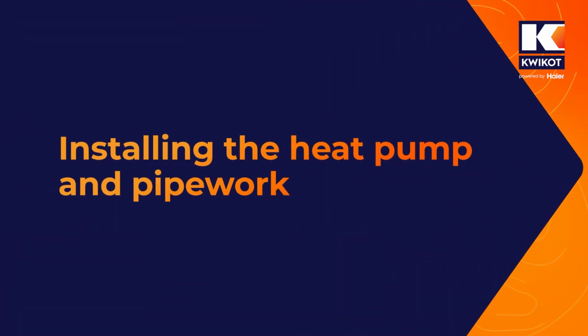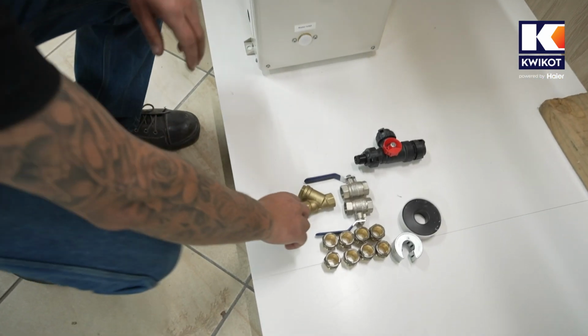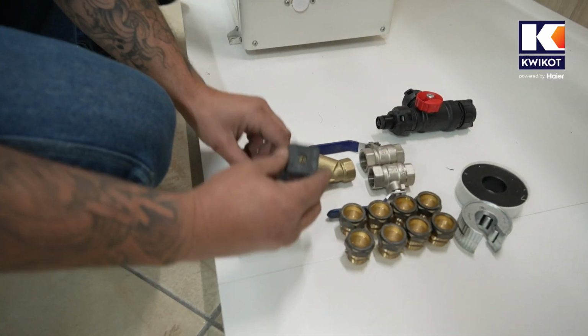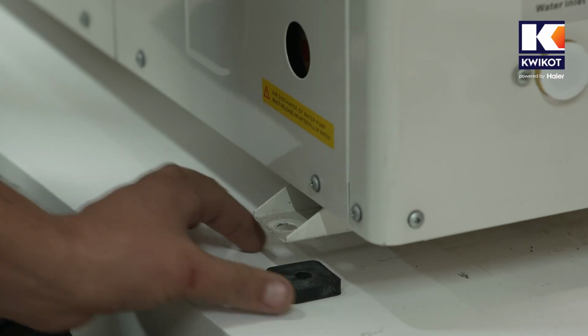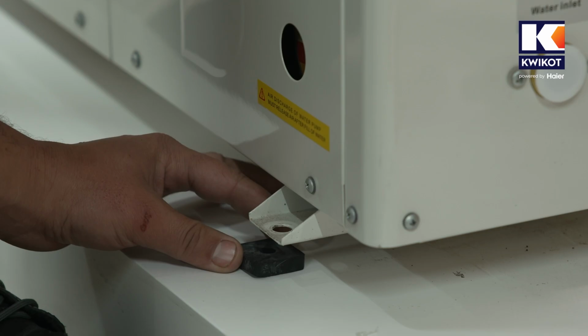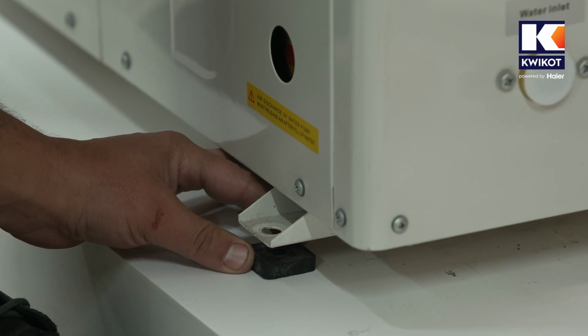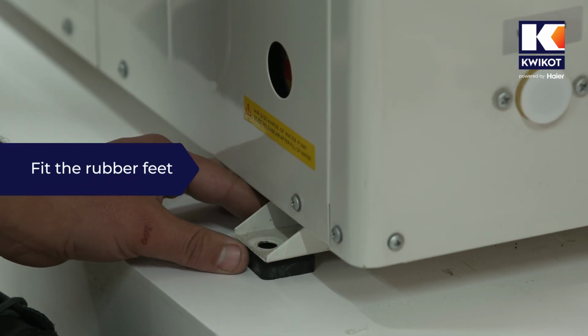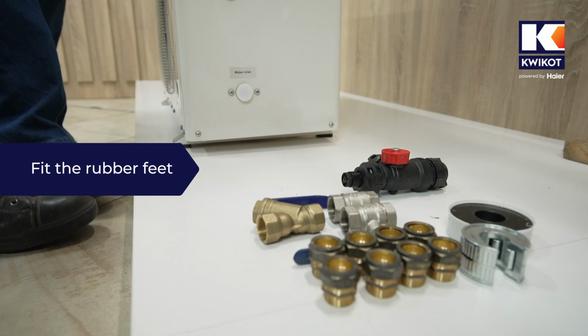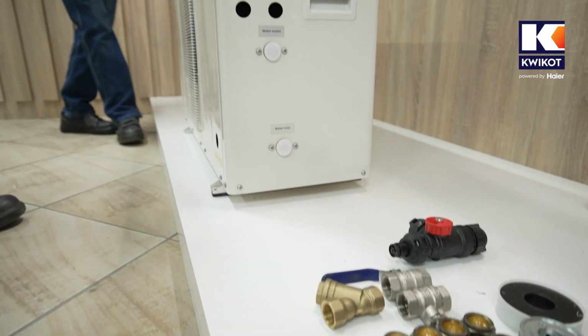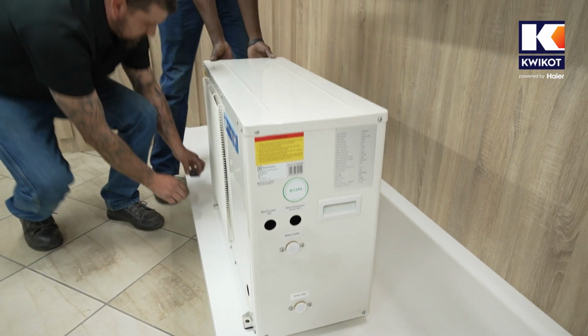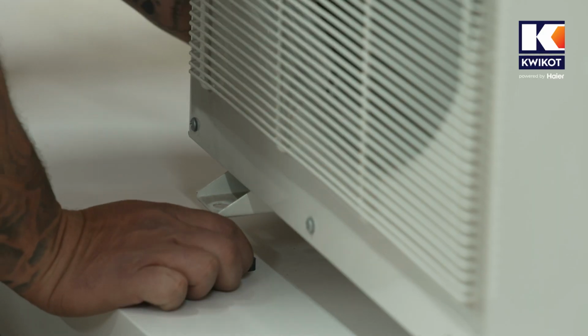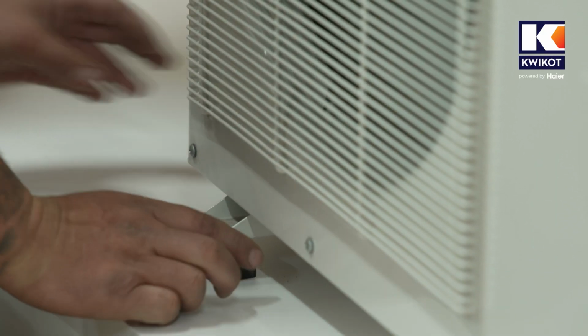Installing the heat pump and pipework. So we've positioned the heat pump on the floor directly below the water heater, which is positioned on the wall above. Our first step is going to be to lift up the heat pump unit at each side and fit the rubber feet below the brackets in the corner. And then we lower the heat pump over them and repeat on the other corner. These rubber feet will prevent vibration.